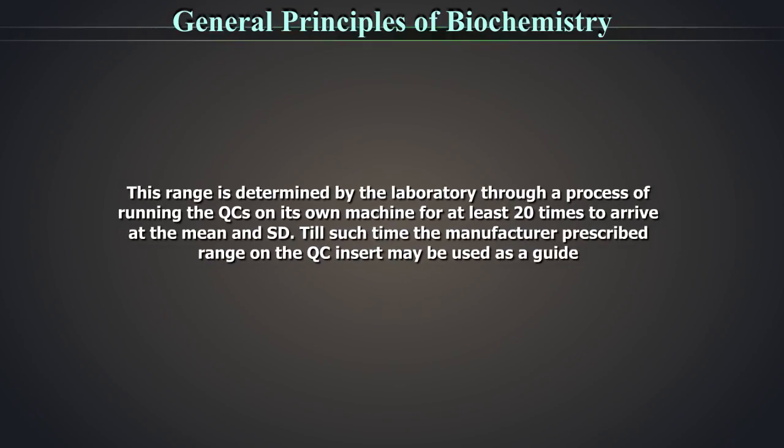On running the QCs, the equipment multiplies the absorbance of the QC with the calibration factor and gives the result. With a valid calibration factor, the QC absorbance values should lie within a specified range. This range is determined by the laboratory through a process of running the quality controls on its own machine for at least 20 times to arrive at the mean and standard deviation.